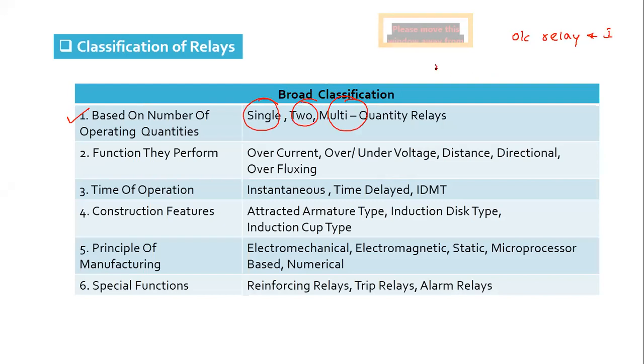There is another relay, the directional relay, or directional overcurrent relay, which requires both voltage and current as input, so it is a two input relay. There are some relays which are multi input relays, requiring more than one quantity as input, maybe two quantities.